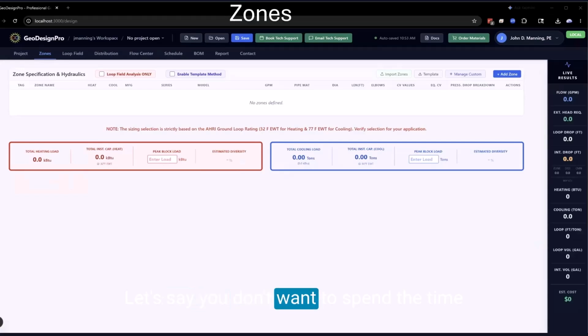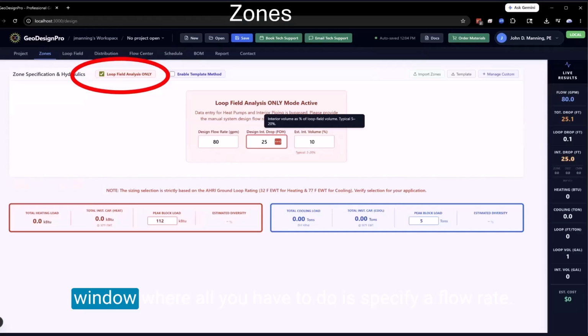Let's say you don't want to spend the time to build out all your heat pumps, and you want to look at just analyzing the loop field. As soon as you check that box, you get a pop-up window where all you have to do is specify a flow rate. Maybe you know the nominal tonnage of the building. Throw in a flow rate that corresponds to that tonnage, somewhere between 2.25 and 3 GPM per ton. The internal pressure drop, you're just putting in as a guess of what you hope the pressure drop of the internal piping to be.